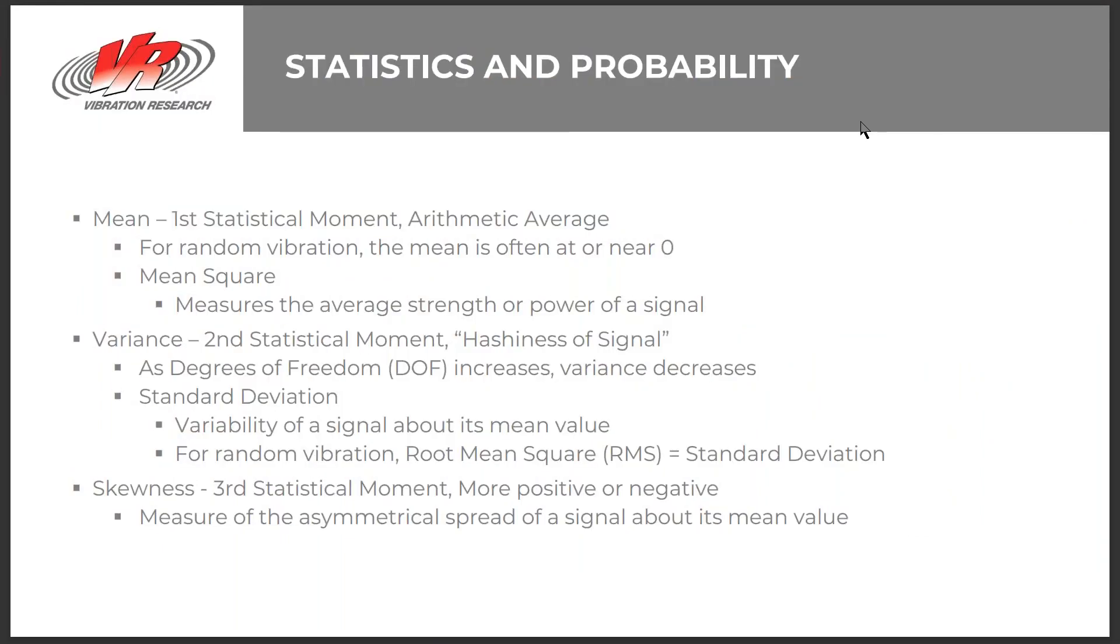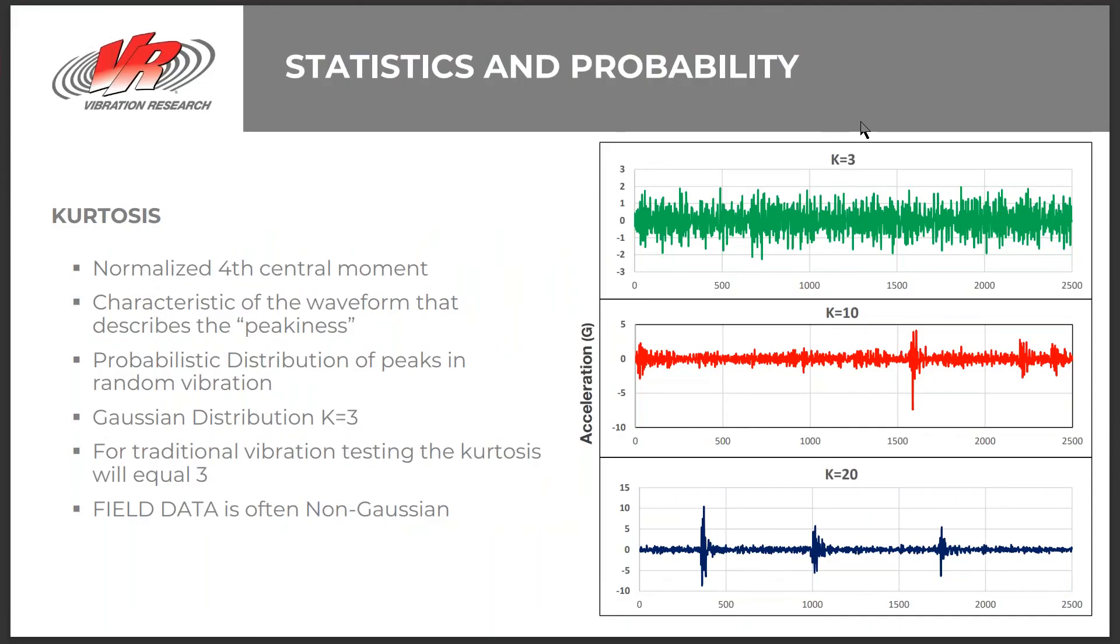A little about statistics. There's four in vibration testing that we primarily concentrate on. The first one is your mean or mean square value, which is where we get power. Second is variance. It describes the hashiness of a signal or variability of the signal around the mean. And skewness is the measure of the asymmetrical spread of a signal about its mean value. And the fourth is kurtosis.